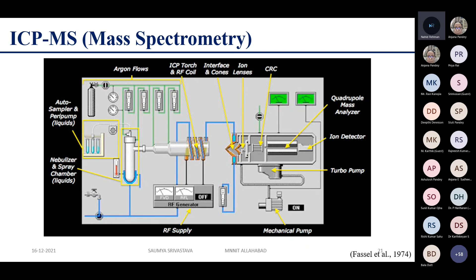And the rotary pump ventilates between the two into several hundred Pa conditions. The path of the ions pulled through by the sampling cone and the skimmer cone converge into the mass spectrometer through the ion lens. The ion lens and the mass spectrometer unit are ventilated to 10 to the power minus 3 and 10 to the power minus 4 Pascal respectively by the turbomolecular pump.